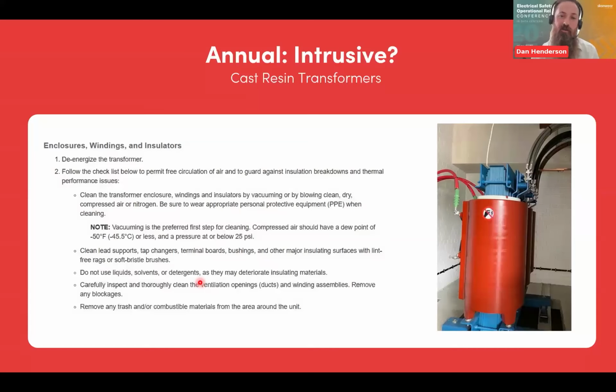What I will say is a lot of cast resin transformers, if you look into the manuals, it'll say 12 monthly. It needs to be vacuumed up of any debris, wiped down, cleaned, check tightness of connections, which in theory is a fairly quick task. But obviously, because of the exposed conductor, you're not going to be doing that live. So you need to isolate it and earth it or ground it so that I can actually get access to the contacts in order to do that. And again, this might be a bit of contention, but something to take away is just to have a look at that. Because obviously it's difficult to get a shutdown every 5 years. So trying to get a shutdown every 12 months to do this maintenance might not fit with your maintenance strategy or your business's projected downtime. So I would just say, definitely refer back to your O&M manuals on that one.